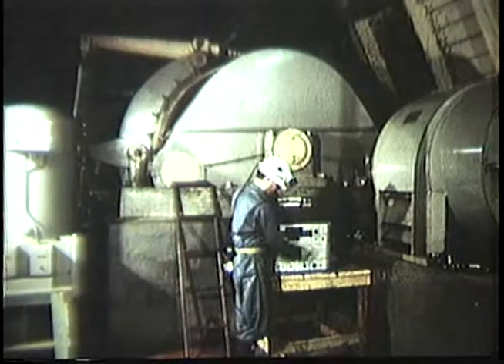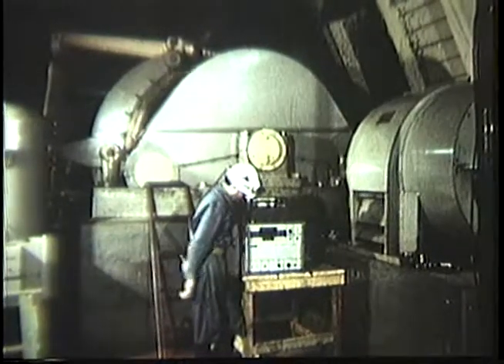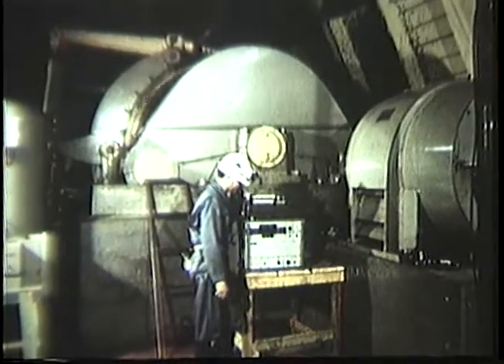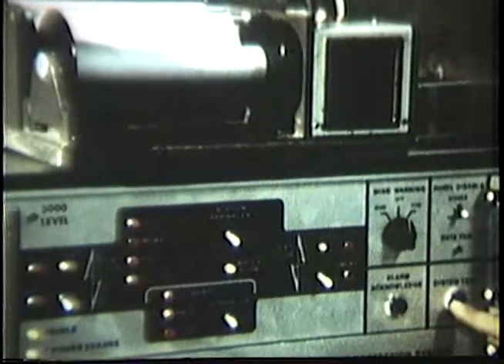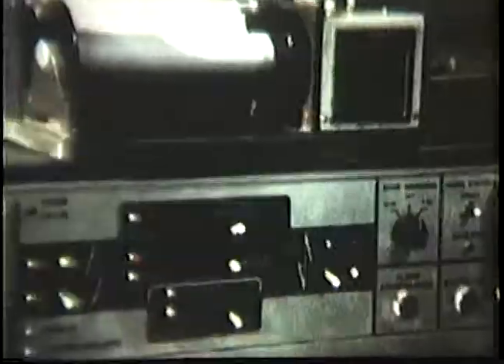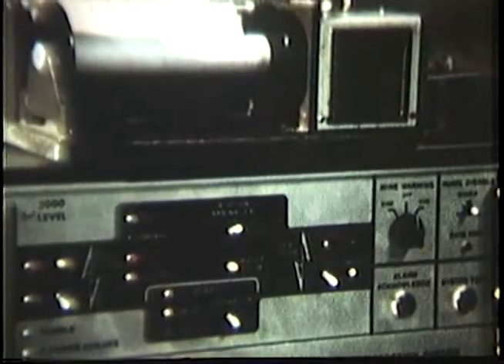The surface control unit is the nerve center of the fire protection system. It reflects the pulse of the mine and instantly alerts the operator of trouble even if fire breaks out in unattended sections of the mine. A test feature allows checking of the system at each level as desired by the operator. If primary power is interrupted, up to four hours of continuous operation is permitted by switching to internal battery power.